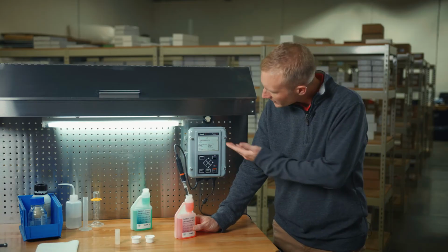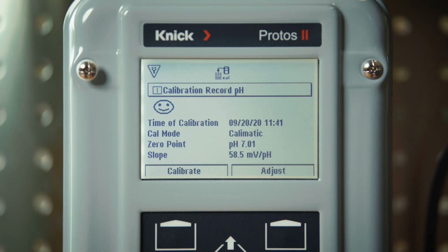Here you can see we have a timestamp of our calibration followed by the calibration mode and the specific values of the 0 point and slope of the electrode. The SensoFace icon in the top left corner of our display indicates the status of our calibration. We have our 0 point displayed as a pH value, followed by the slope displayed as millivolts per pH, and finally a smiley face indicating a successful calibration.